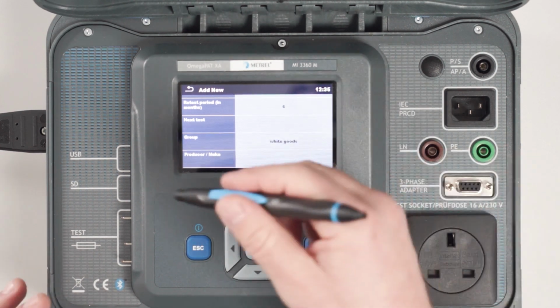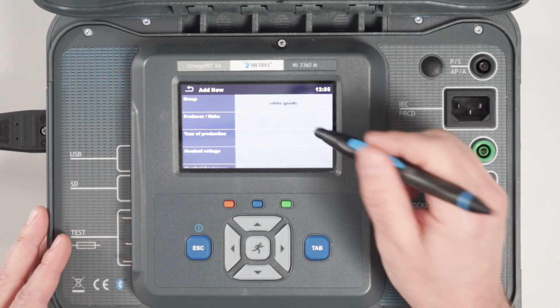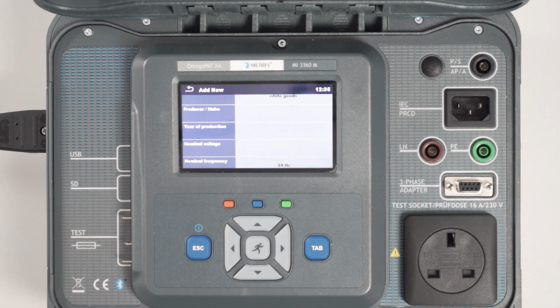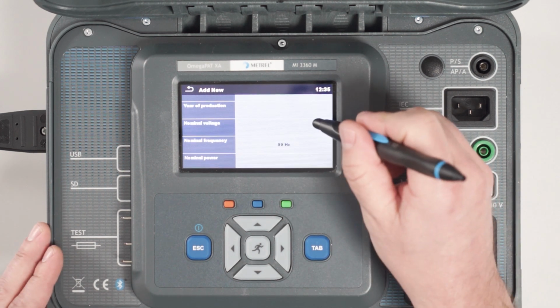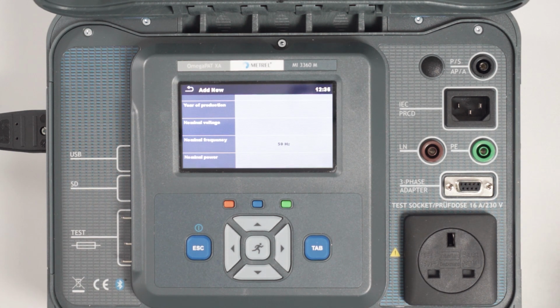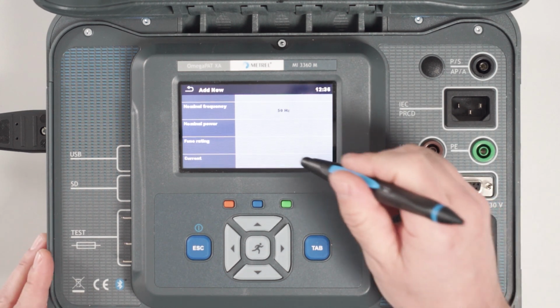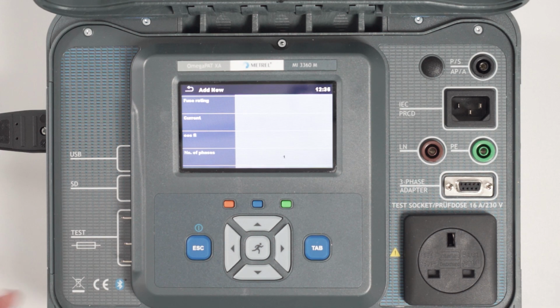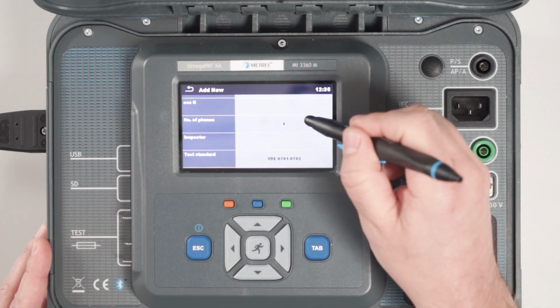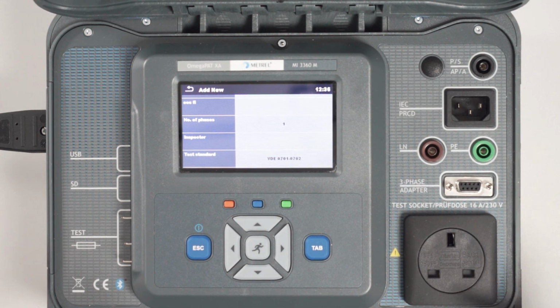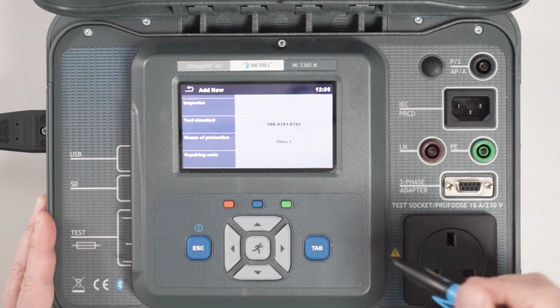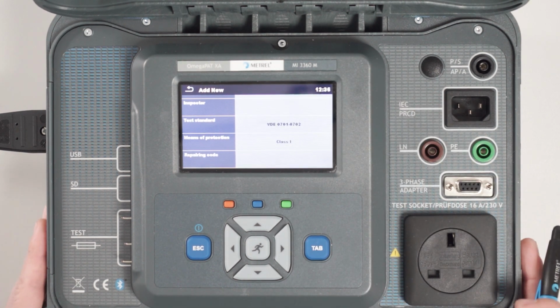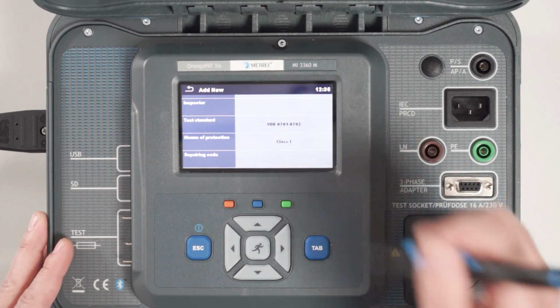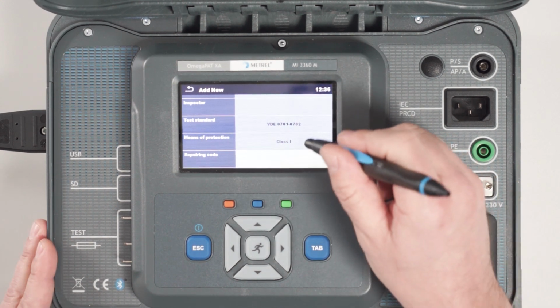And then we have already a group of appliance parameters. We can add producer, make, year of production of the appliance, what kind of nominal voltage the appliance is using, then the nominal frequency of the appliance, also nominal power, fuse rating, current consumption of the appliance, cosine phi, and number of phases, whether we have a single-phase or 3-phase appliance. We can add according to which test standard this appliance was tested. These standards can be added manually.